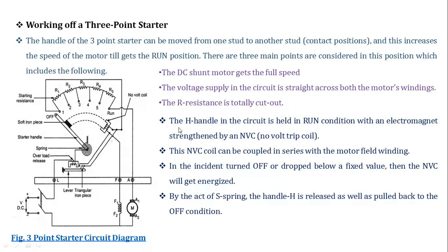Third, the handle H in the circuit is held in the run condition by an electromagnet energized by the NVC. NVC stands for no volt trip coil. With the help of the NVC coil mentioned over here, the handle can be kept in the run position by the electromagnet. This NVC coil is coupled in series with the motor field winding.